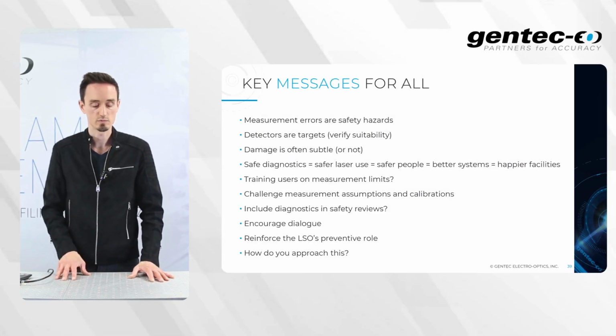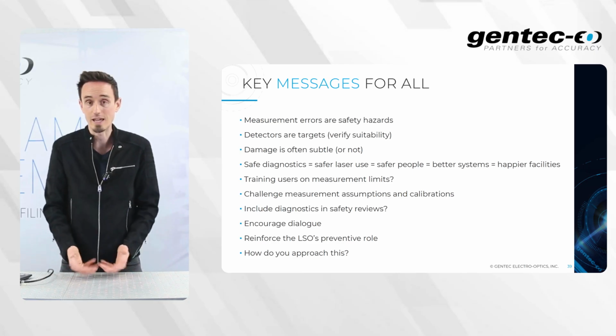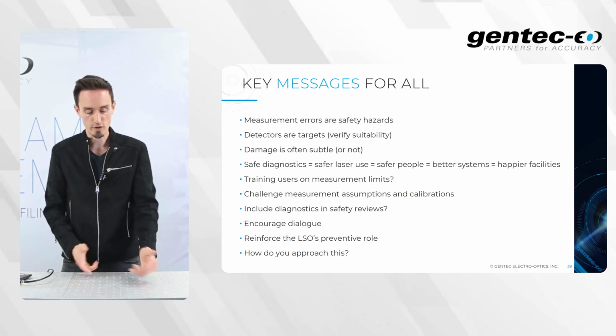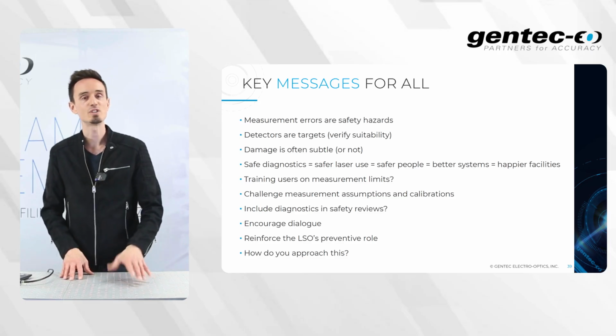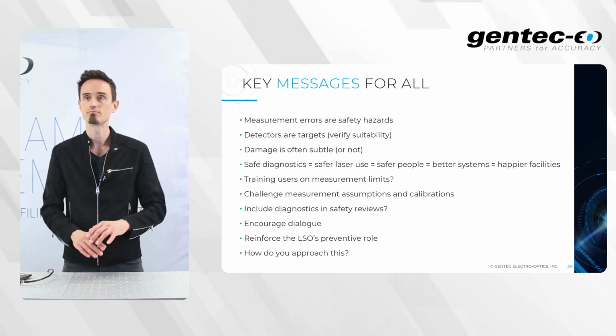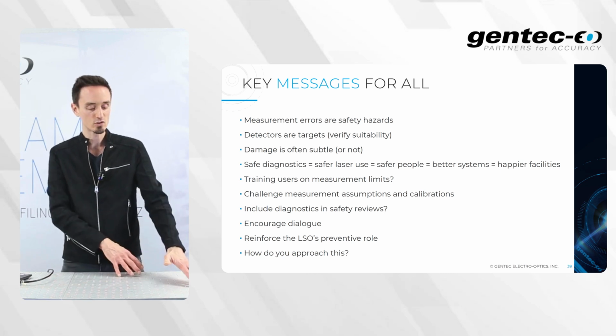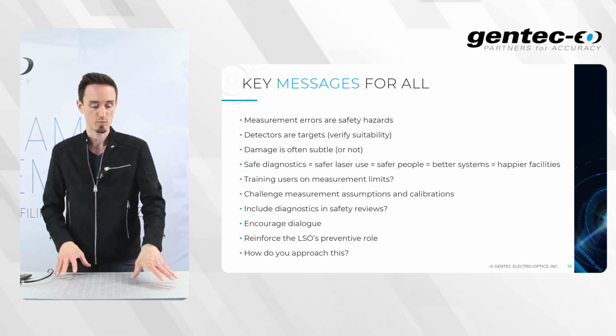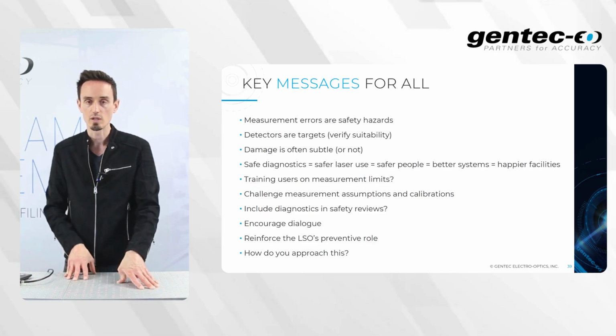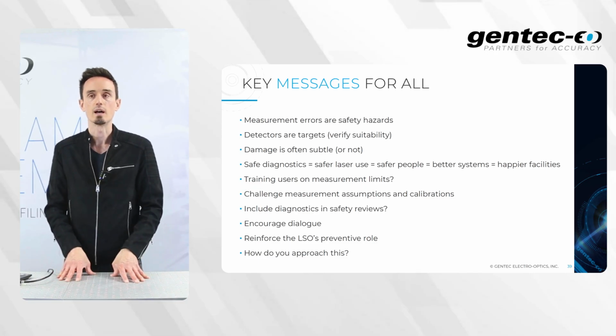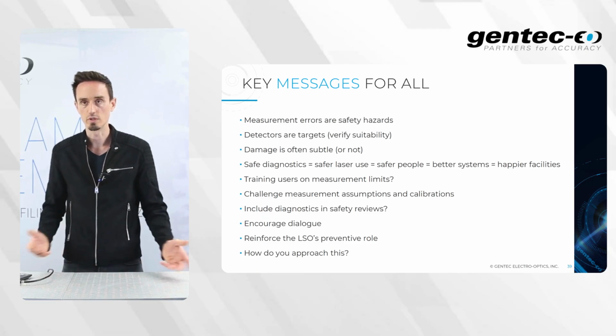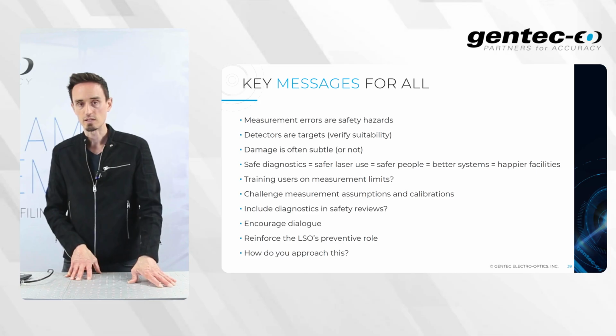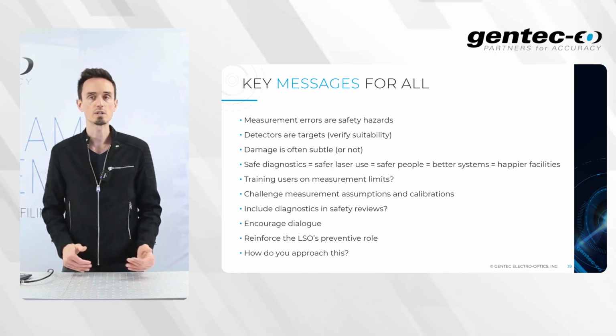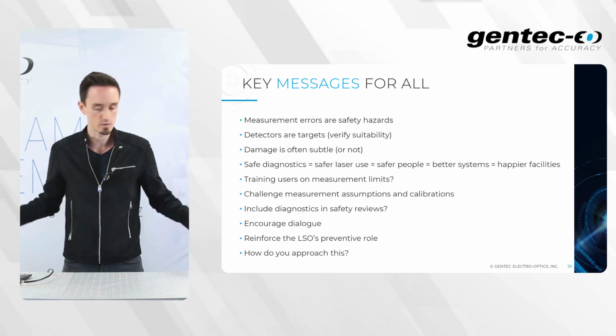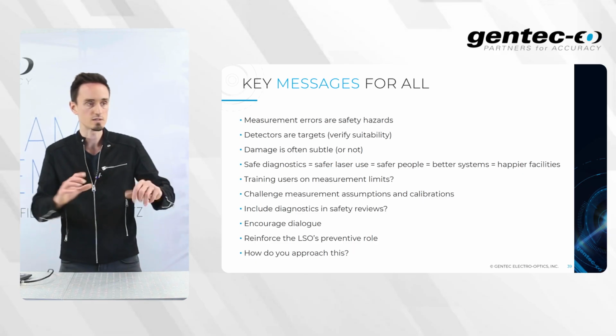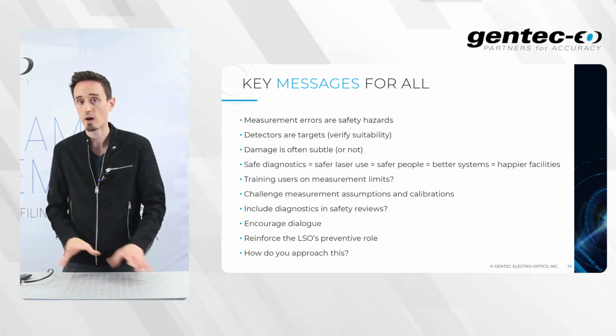So, key messages for all. I think we established that measurement errors are a safety hazard, right? Detectors are targets. We need to verify their suitability. Damage is often subtle and internal, and sometimes pretty obvious. Safe diagnostics will drive safer laser use, make people safer, resulting in better systems and, in the end, happier facilities, right? Do we need to train users on measurement limits? I think so. Do we need to challenge measurement assumptions and calibrations? Yep. Do we need to include diagnostics in safety reviews, not just proper enclosures and strategies and signage and curtains and so on, but also talk about parameters as well?